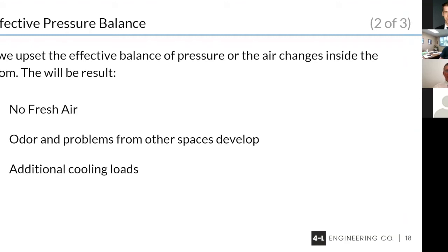It is important that everybody has fresh air into their space. We bring this fresh air in for a couple of reasons. Number one, the fresh air that we bring in is usually introduced into everybody's space in some way, unless they close off the damper. And sometimes they'll do that in some buildings because when you bring in the outside air, it's at a higher temperature, and sometimes a lower humidity, but it adds air conditioning load to the space. So people like to close this outside air off. Don't do it. It's designed to bring fresh air into the space, to eliminate odors that are developed in there, and it's designed to handle that load.